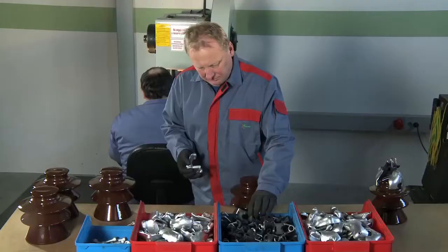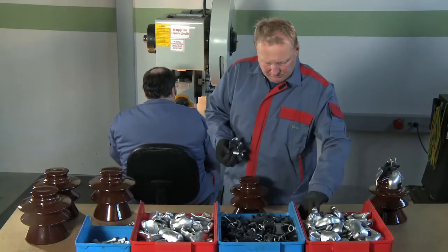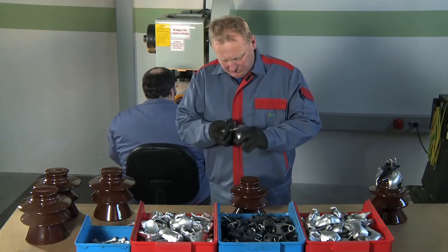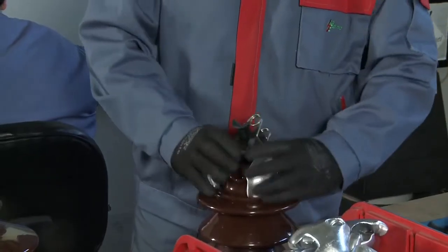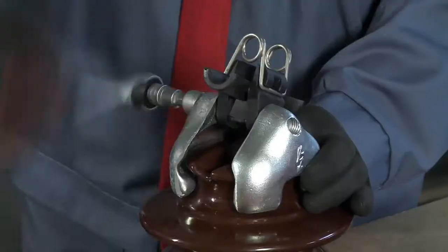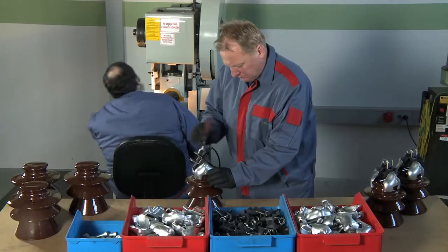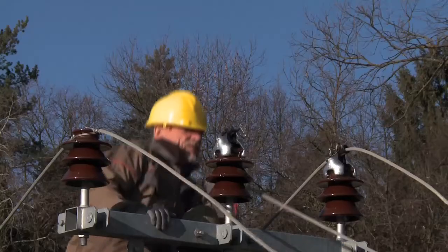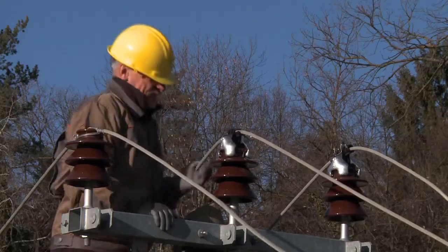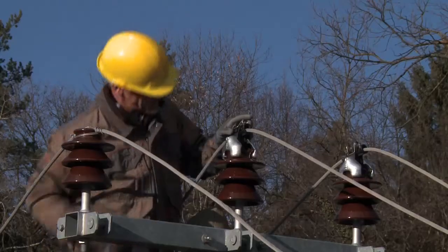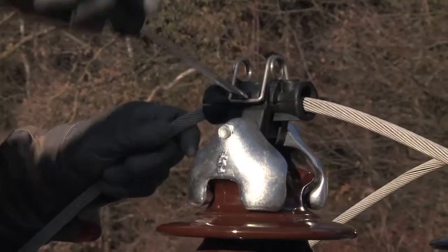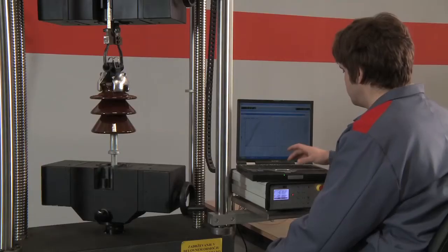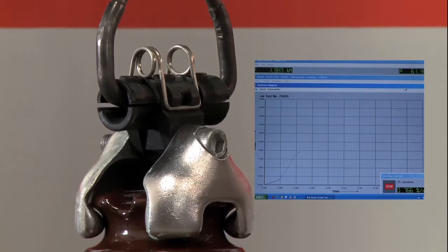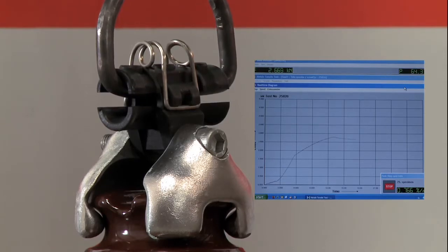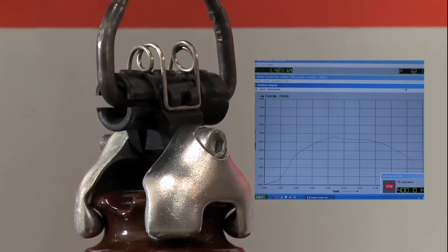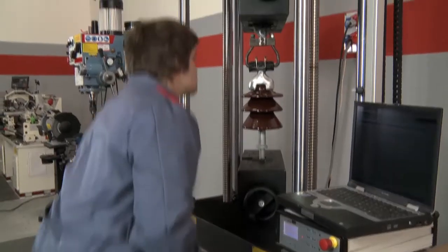Our first patented product is the autonomous spring clamp with an insulating insert. It enables the simple and quick fastening of a conductor onto existing or new post insulators. The spring clamp's essential advantage is that it diminishes partial discharges at the point of fastening the conductor onto the insulator. A stainless spring with an accurately chosen pressure point enables a permanent elastic tie, which is meant to dampen vibrations and ensure the predetermined conductor pull strength. Our autonomous spring clamps are suitable for fastening conductors of up to 120 millimeters in cross-section.